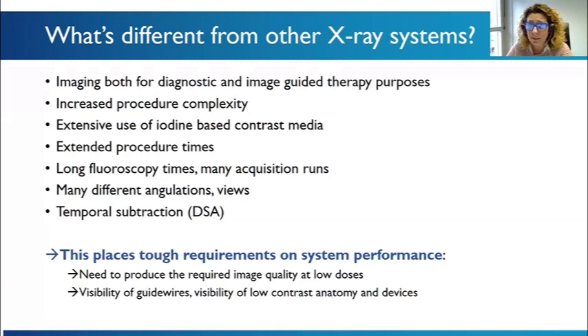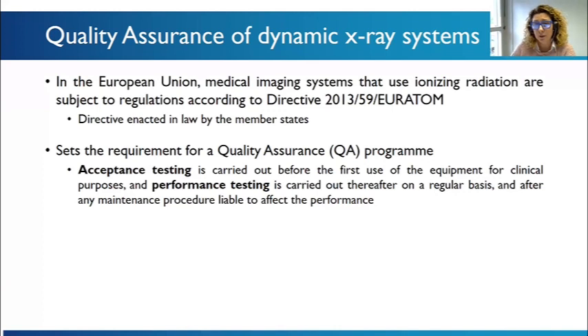So all these differences place a tough requirement on system performances, because this system needs to produce required image quality at low doses, and mostly it is about the visibility of guide wires, visibility of low contrast anatomy and devices. And moreover, in the European Union, medical imaging systems that use ionizing radiation are subjected to the European directive, which was included in the national legislation a few years ago.